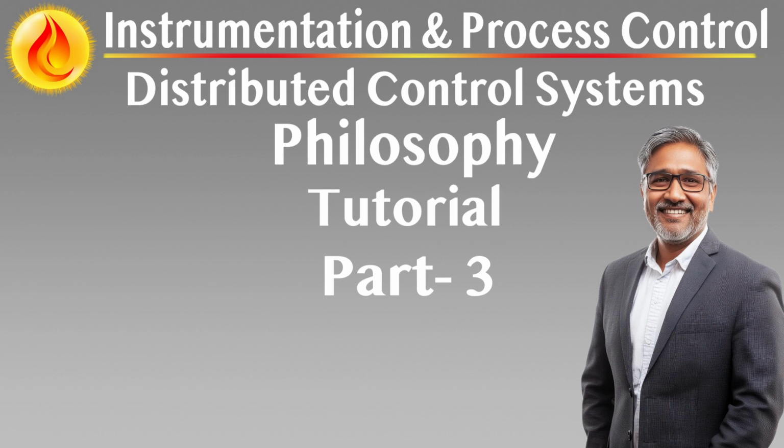System configuration and logic. Modular, IEC 61508 certified safety PLC architecture. FGS logic shall run on a SIL 3 rated PLC or SIS, modularly scalable and physically segregated from non-safety systems. The system supports deterministic scan cycles and redundant execution paths, 1oo2D or TMR as applicable.